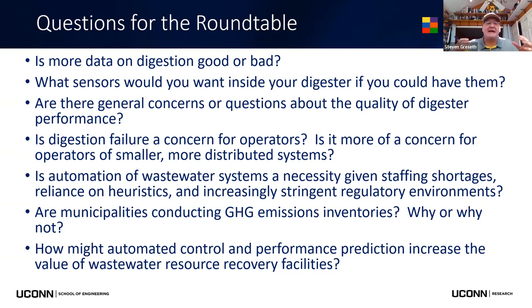And supply chain specialists thought they could use math and statistics to make the supply chain better. But in fact, all of their adjustments made it worse. They magnified the errors. When I took that idea and looked back on operating wastewater plants, and in particular anaerobic digesters, I think there is a sound idea that can be applied to digestion: variation is extremely bad. Temperature variation, food variation. The previous speaker talked about increasing loading, and sometimes you have to do that, but really that's setting the digester up for a very negative situation. So I think the instruments and the tracking of the data is spectacular, but my concern is that people will try to rely on that instead of thinking about simple things like eliminating variation in temperature, feed, and mixing in your digester.